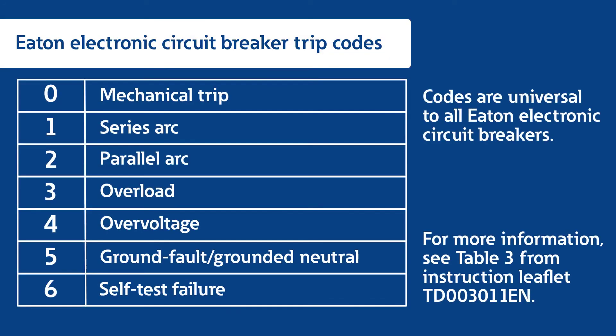But what does each trip code mean? They're actually quite easy to understand. Each number in the trip code column corresponds to the number of blinks displayed on the breaker's LED. For example, if the LED displays a pattern of two blinks, this indicates that the breaker detected a parallel high current arc, perhaps caused by a nail or screw piercing an electrical cord.